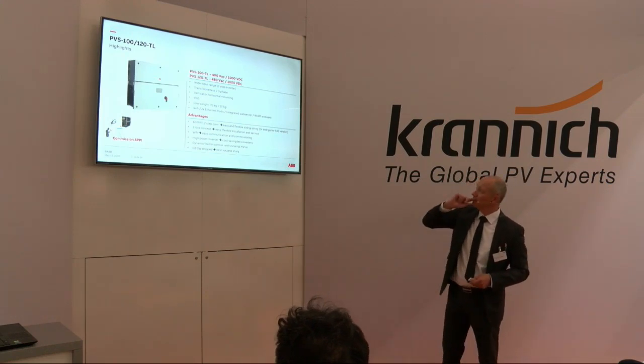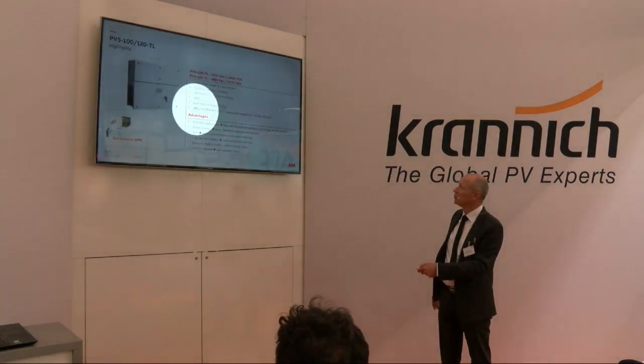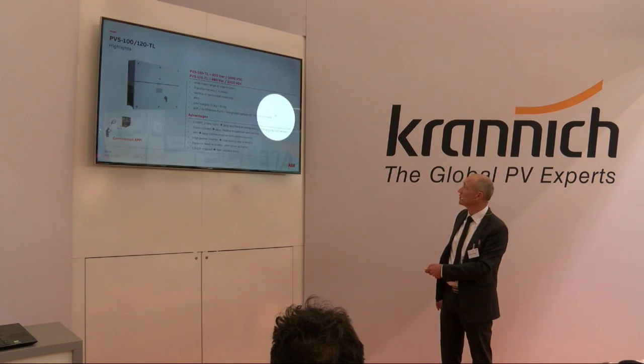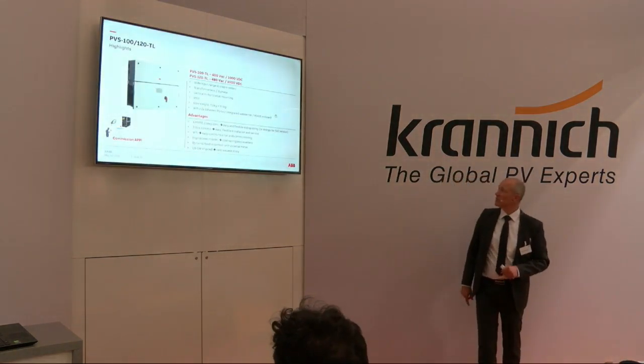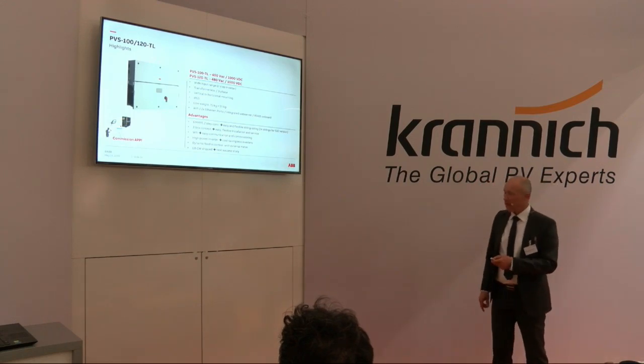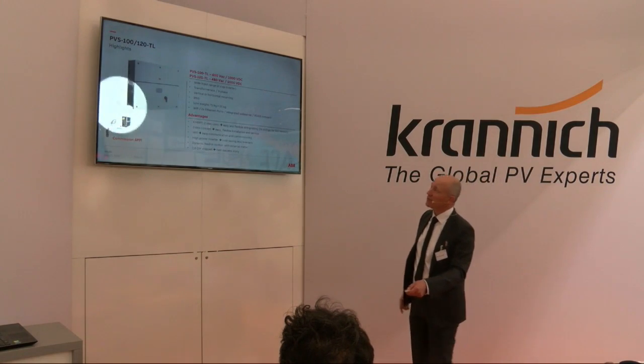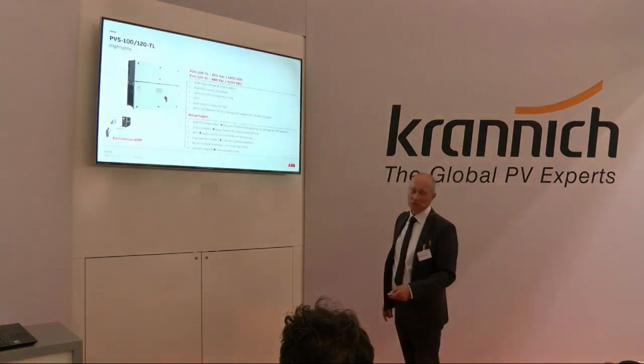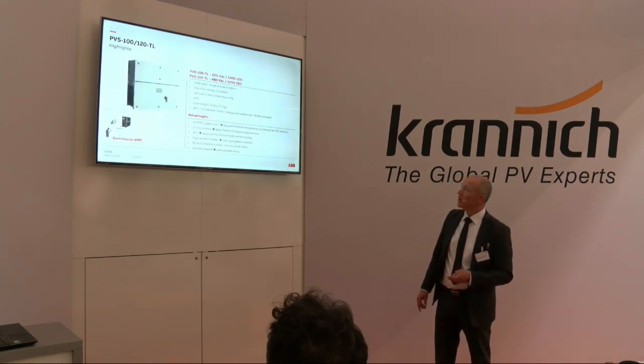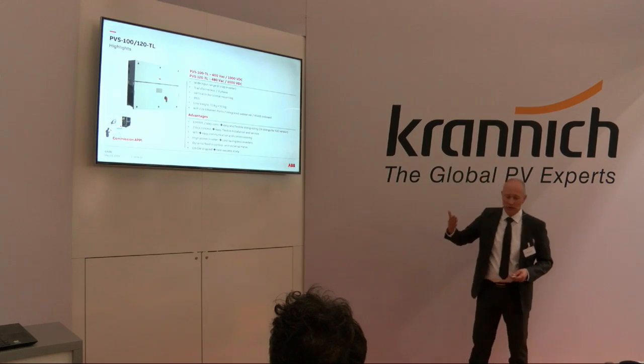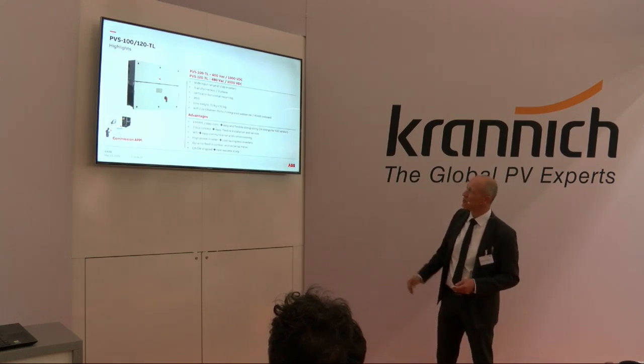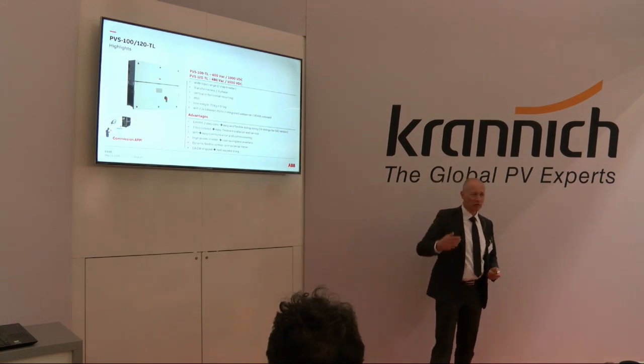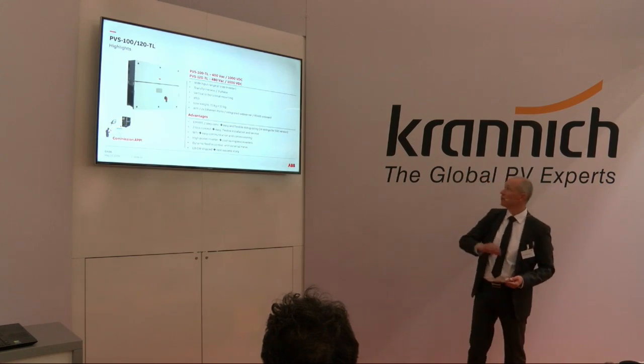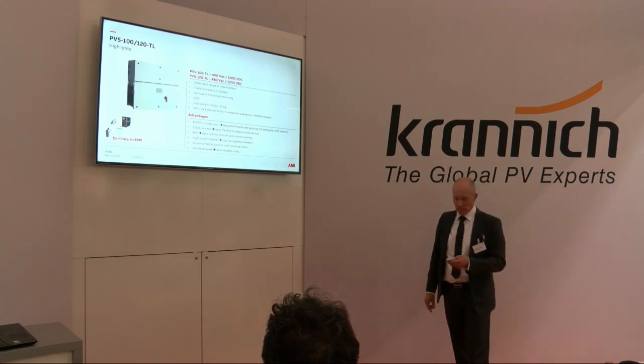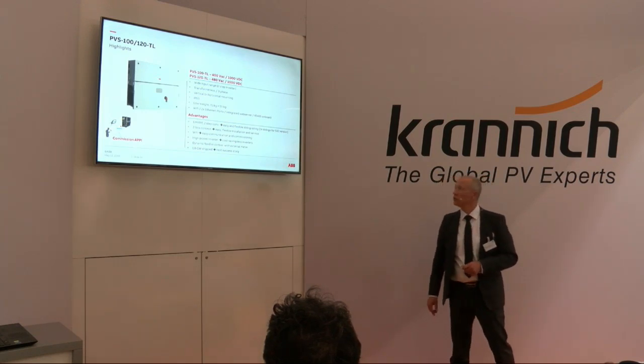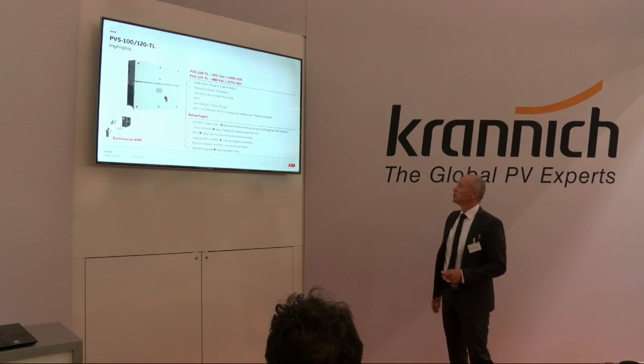If you look at the communication, we have Wi-Fi on board, 2 Ethernet ports, an integrated web server, RS485, everything that is needed. This is also a SunSpec compatible inverter, and we deliver the inverters with a QR code on the side. If you have the installer app, the commissioning app, you can scan this code and say, please install the German grid code, or please install the RS485 communication bus. Then you can commission up to 50 of these inverters in one shot, which is very useful.